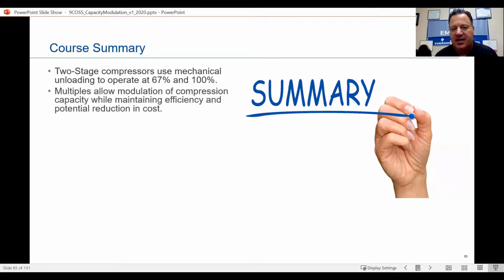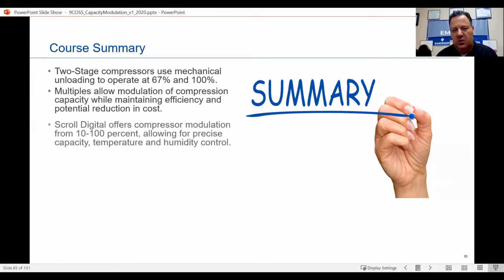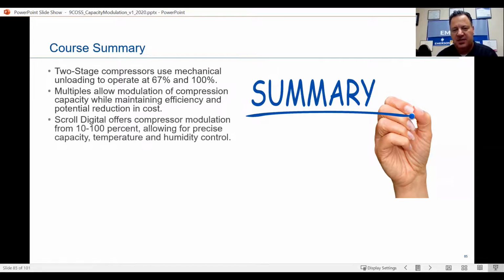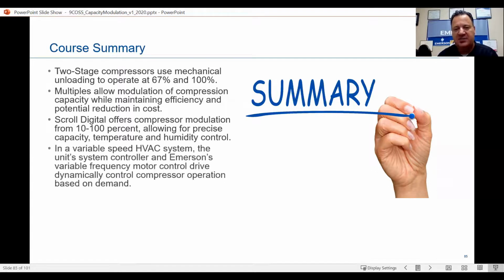Multiples allow modulation of compression capacity while maintaining efficiency and potential reduction in cost. Scroll Digital offers compressor modulation from 10 to 100%, allowing for precise capacity temperatures and humidity. Remember that temperature within a half a degree. And last but not least, in our variable speed HVAC systems, the unit system controller and Emerson's variable frequency motor control drive dynamically control the compressor operation based on demand.